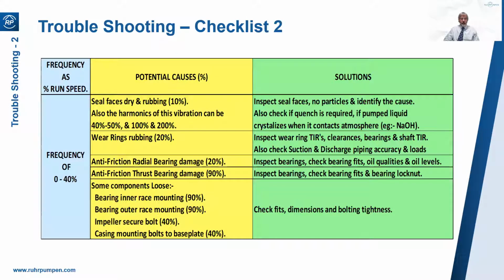So looking at the first of the 8 slides, vibration frequencies, 0 to 40% of running speed. 10% of the time, seal faces are dry. 20% of the time, wear rings are rubbing. 90% of the time, you've got thrust bearing damage. And 40% of the time, casing mounting bolts are loose. Well, that's a really easy one to check. So that was the first thing I would check straight away if I had high vibration in this frequency, 0 to 40% of running speed. And after that, then take the pump out of service so that you can look at the bearings.